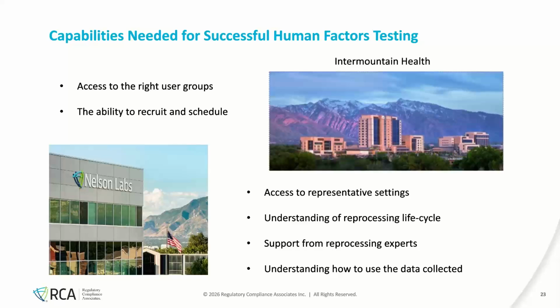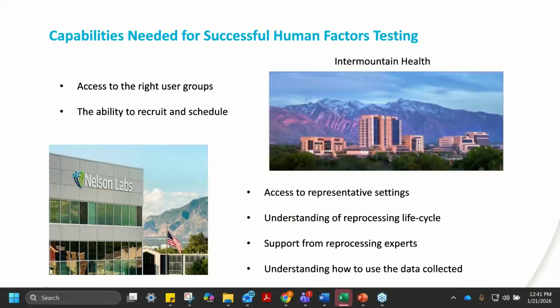Support from reprocessing experts comes in handy when you're trying to figure out what all needs to be included in this and what doesn't need to be included. The lines between human factors testing and what falls into the reprocessing validation can get a little blurred. And then understanding how to use the data that you collected. Do you need to write up some risk assessments? Do you need to better define your failure modes? Do you need to make adjustments to your IFU? So that's really important for running a successful test.